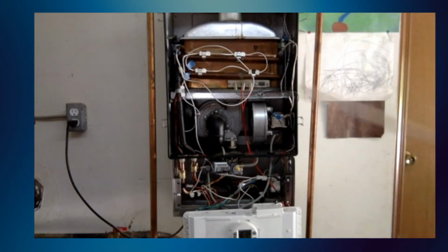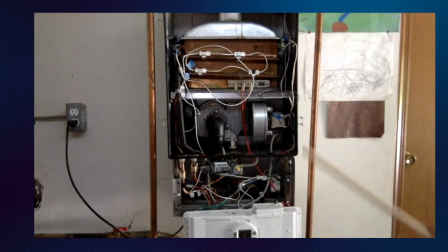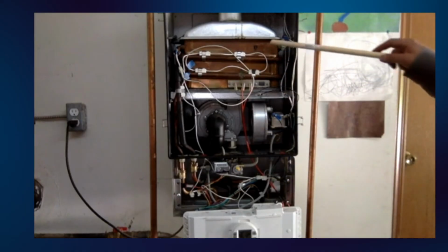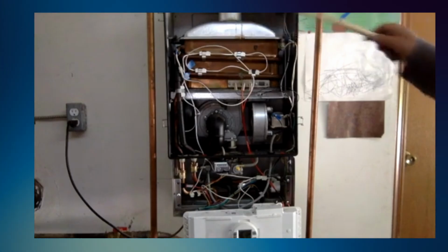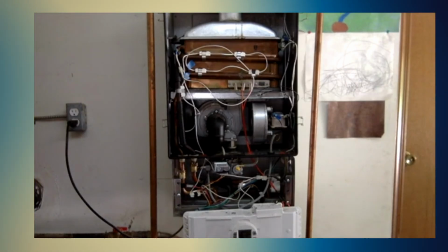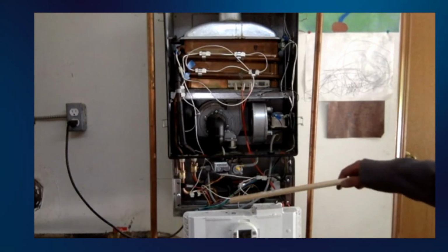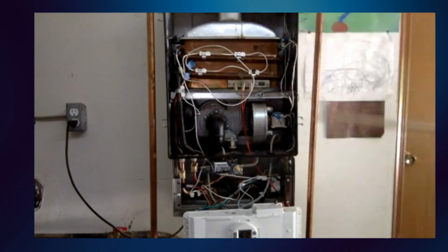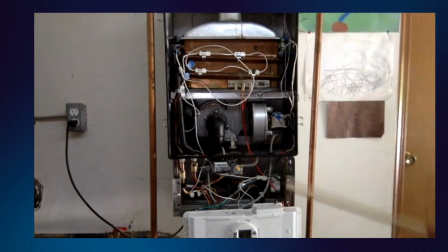The 10th possible cause is a fan, air pressure, or combustion control issue. Many modern Bosch boilers check fan operation and airflow before ignition. If the fan is weak, blocked, or not being read correctly, the boiler may not reach the right conditions for ignition. This can also connect with flue or air intake problems.